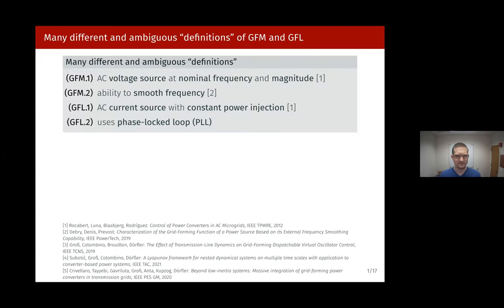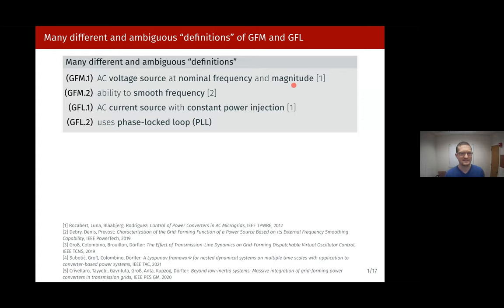Before jumping into the details, one key motivation for this consortium effort is that there are no really clear or precise definitions of what we mean by grid forming control. One of the earliest definitions basically says a grid forming converter is an AC voltage source at nominal frequency and magnitude. By that definition, even a large-scale power station would not be grid forming, so you can immediately see the problems with this.